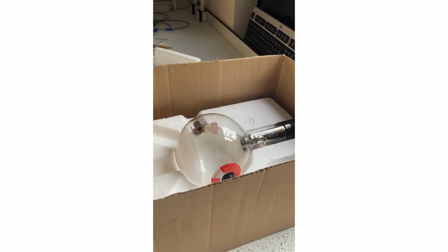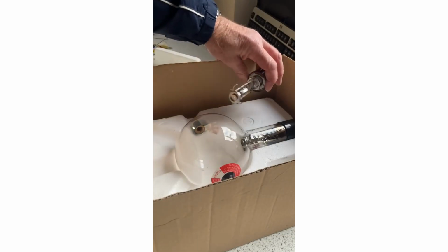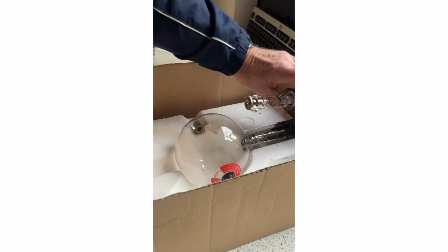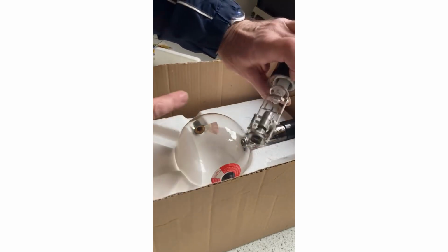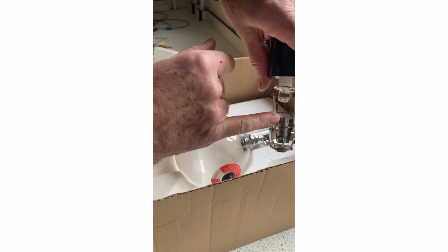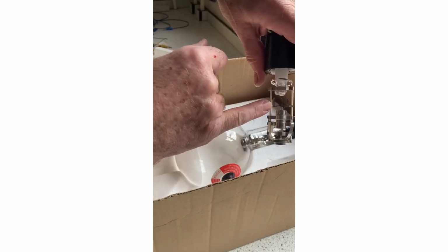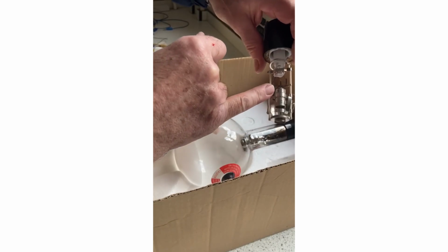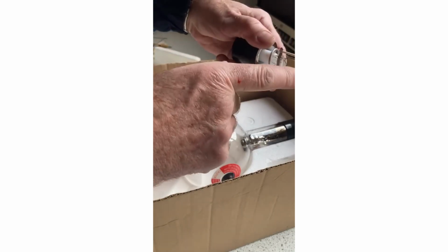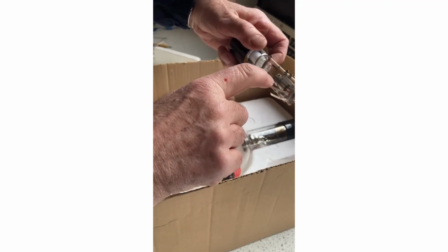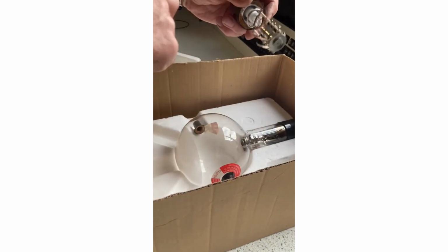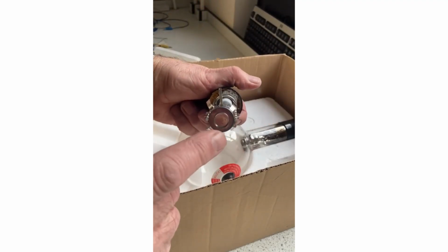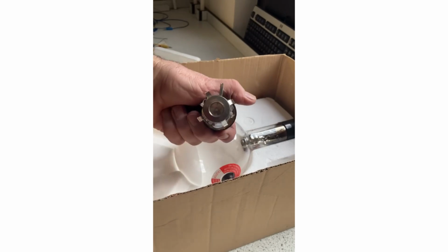Now, I have an older tube that the heater got damaged on, and this is the business part of that. So the cathode is here with heating connections, and the high voltage connection, and the anode is connected via that, which goes to a connection on the other side, and the window is the whole circle in the middle of this.